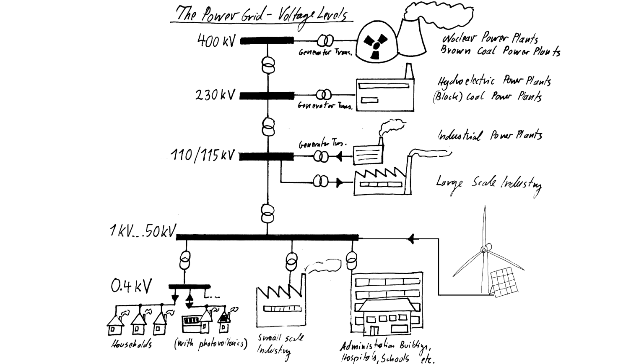So, why do we have so many different voltage levels on the power grid? Well, high and extra high voltages allow the transport of large amounts of energy over large distances at acceptable efficiency and with conductors of comparatively small conductive cross-section areas. On the other hand, these voltages require a lot of safety measures and are much too dangerous for households. The different voltage layers are all a trade-off between cost efficiency, required power handling capability and safety.